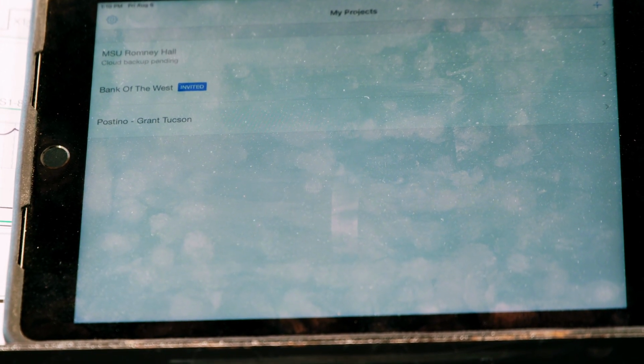I literally just finished commissioning the system, like 15 minutes ago. I assigned the last few aux sensors to the system. The other issue we came across - you have a great system here in the building, very granular. When you look up all your light fixtures, the linear light fixtures each have their own address, so it's very granular. You can really do a lot of programming and adjustments with that. Unfortunately it didn't show on the print, so that's why it took a little longer for programming, because I had to address every single fixture.